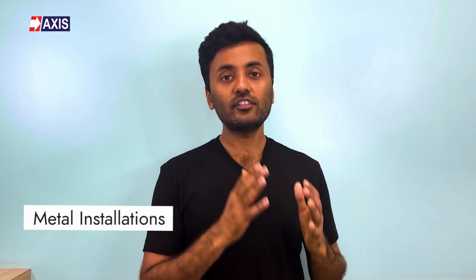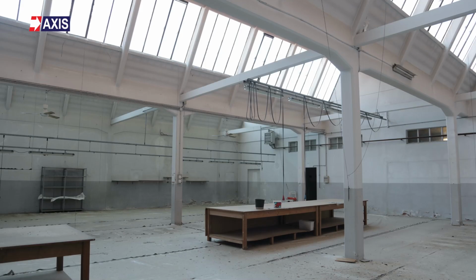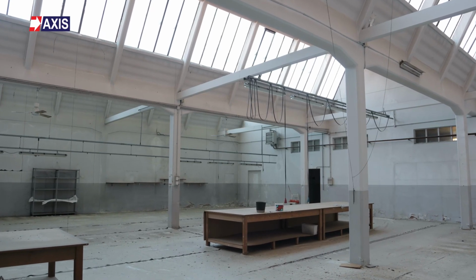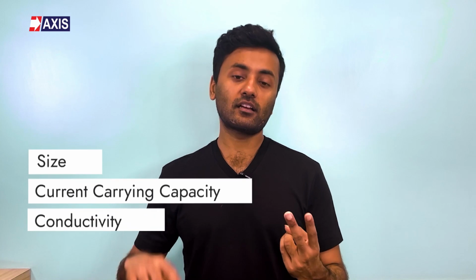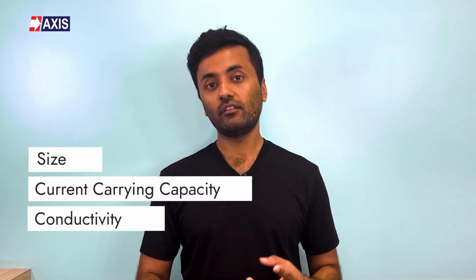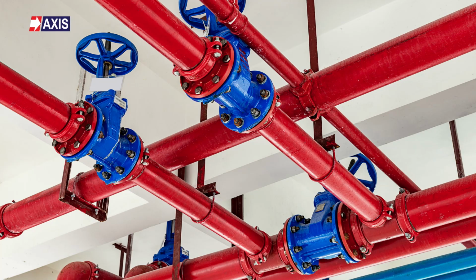Metal installations. These could be large interconnected metal structures within the building, such as steel beams or reinforcements. They can serve as a down conductor provided their connections are permanent and that they meet the minimum requirements like size, current carrying capacity, and conductivity for down conductors. However, there are some exceptions to this. Pipes or conduits carrying flammable or explosive materials cannot be used as down conductors. The reason is simply that this equipment might have non-metallic seals or joints which won't be electrically conductive and could pose a risk during lightning strikes.